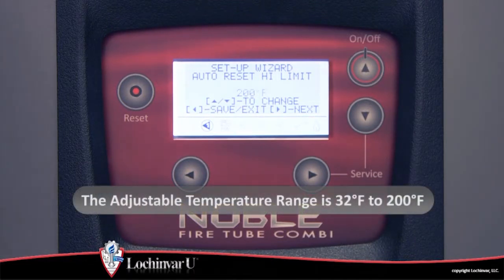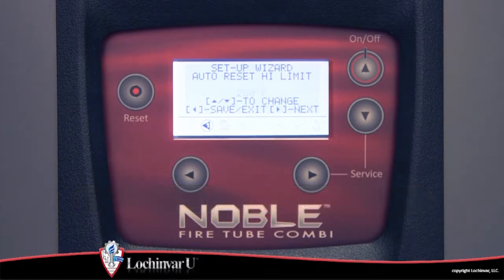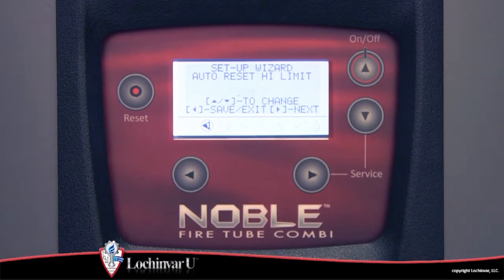The adjustment range for this parameter is 32 degrees Fahrenheit to 200 degrees Fahrenheit. The auto reset high limit parameter should be lower than the setting of the manual reset high limit parameter to avoid nuisance lockouts.